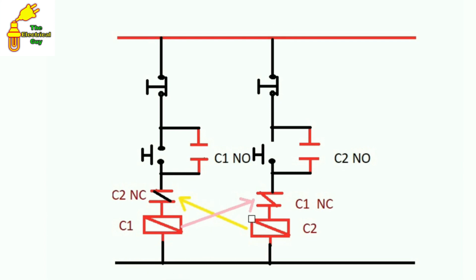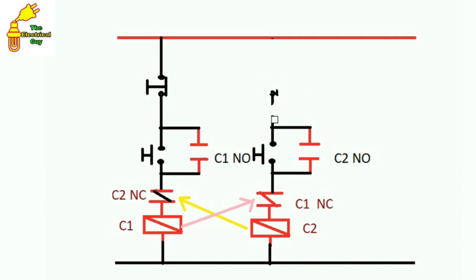You are thinking you know this kind of circuit — this is a circuit of a forward-reverse dual starter. In this we use two contactors and interlock both contactors together so that both cannot turn on at the same time. Now let's modify this circuit a little bit: the two stop push buttons, let's make it a single one. For this, remove this stop push button from here and connect this start push button with this.